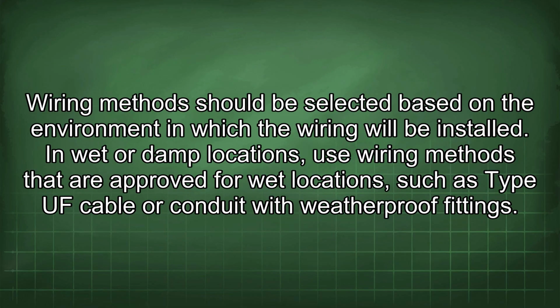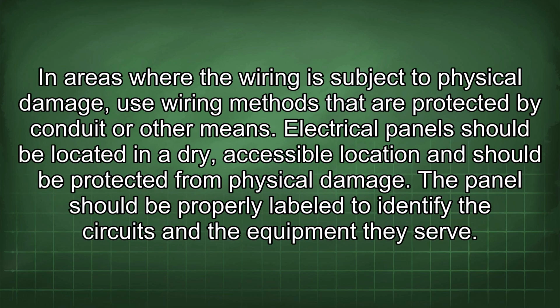Wiring methods should be selected based on the environment in which the wiring will be installed. In wet or damp locations, use wiring methods that are approved for wet locations, such as type UF cable or conduit with weatherproof fittings. In areas where the wiring is subject to physical damage, use wiring methods that are protected by conduit or other means. Electrical panels should be located in a dry, accessible location and should be protected from physical damage. The panels should be properly labeled to identify the circuits and the equipment they serve.